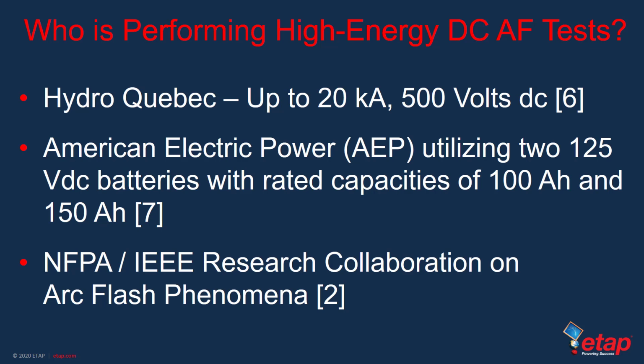I would like to personally thank Kirk and Simon at Hydro-Quebec for providing the footage of some of the higher incident energy or higher current DC arc flash events that we'll see in the next few slides. Bottom line, this slide serves as a transition point between the lower energy photovoltaic systems, which are ruled by the nonlinear characteristics and current limitations of photovoltaic panels, into the world of high current battery power, converter power DC systems, where the amounts of currents are 10 to 20 times higher than we see on these photovoltaic systems.